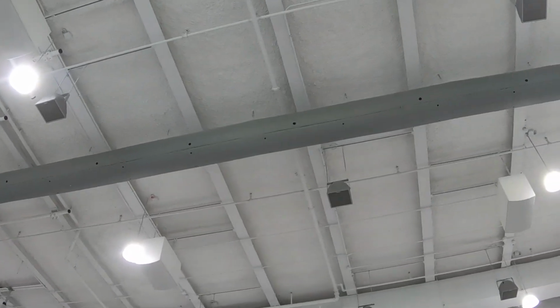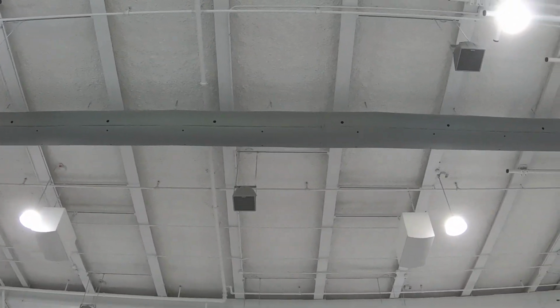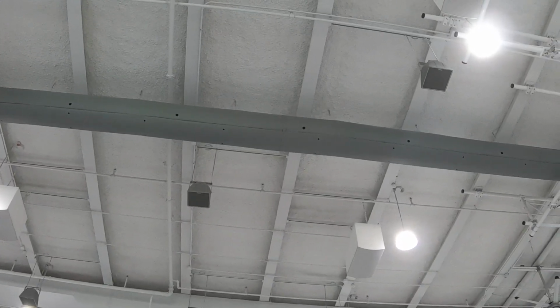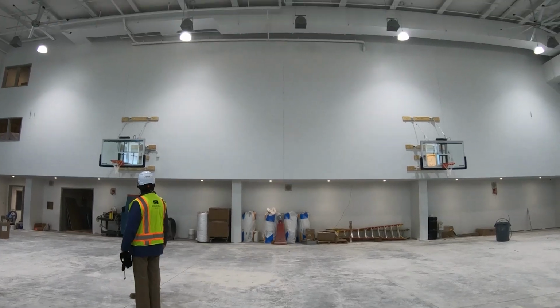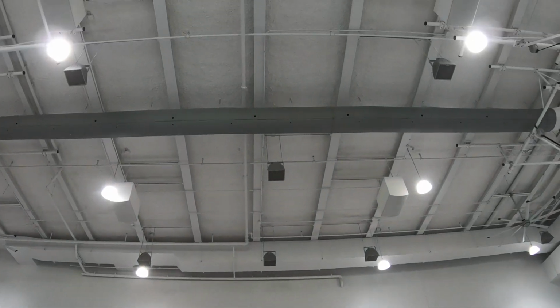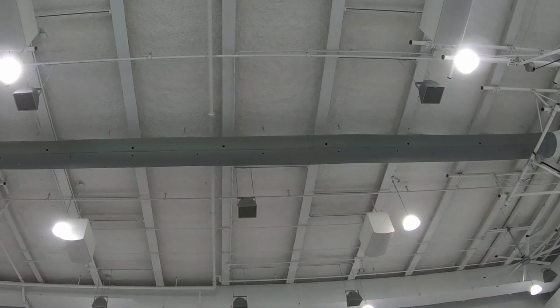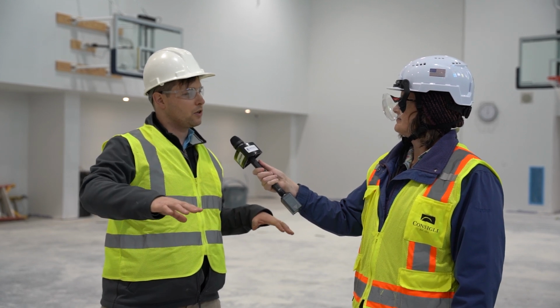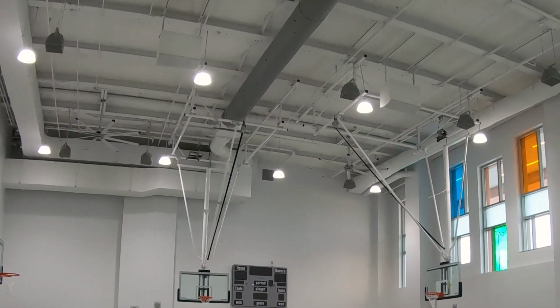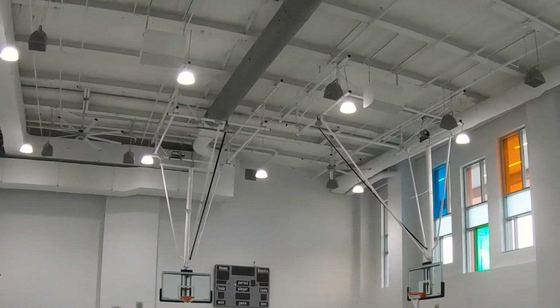A fabric duct — I've never seen something like that before. How new is that, and what are those black holes? It's not all that new, but it is a bit of a niche product. We especially use it in gyms, large auditoriums, and spaces of that larger nature. The upside to fabric ductwork is that instead of having diffusers everywhere, we can put those black holes — nozzles — in the duct that distribute air throughout the space. As HVAC engineers, we're trying to distribute air as much as possible so there are no hot spots or cold spots, and this lets us spread the airflow so it's as even as possible.